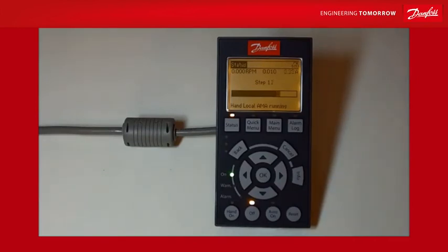Okay, we're on step 12 now, so we've got a little bit more to go. I'm going to tell you a few other things as well. This test is a static test. In other words, a lot of our competitors will do an automatic motor adaptation of sorts. The only thing is that they'll expect to run the motor up to full speed with no load. In other words, you start to knock couplings off and things like this, or knocking belts off, so you can run the tests. This is a true static test and doesn't move the shaft at all.